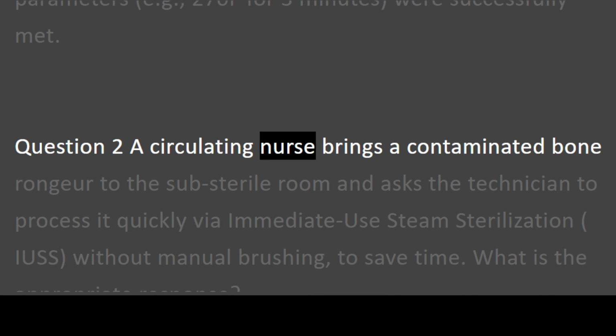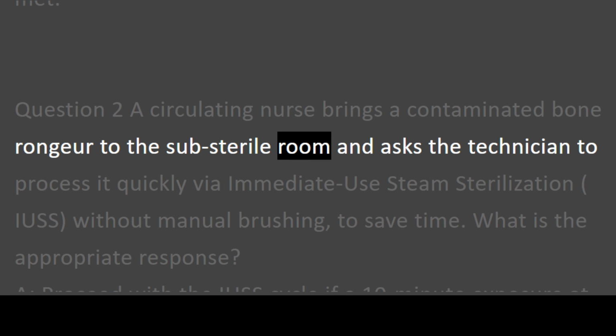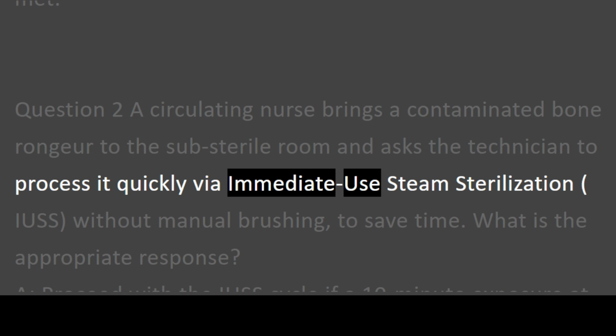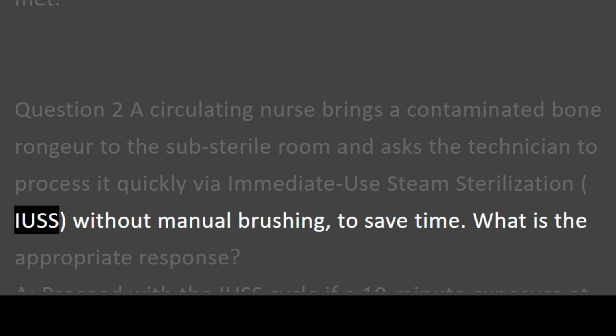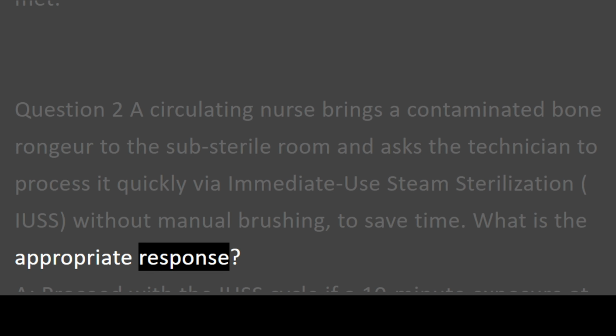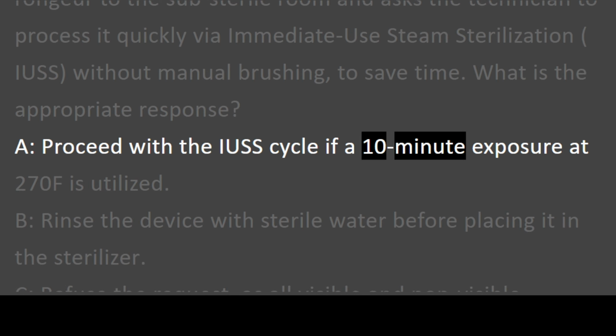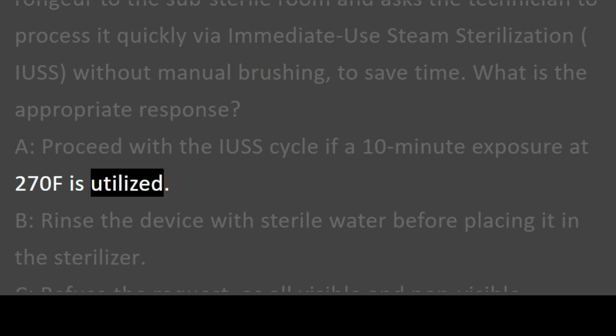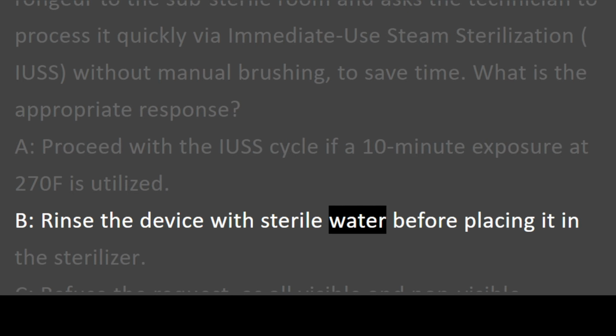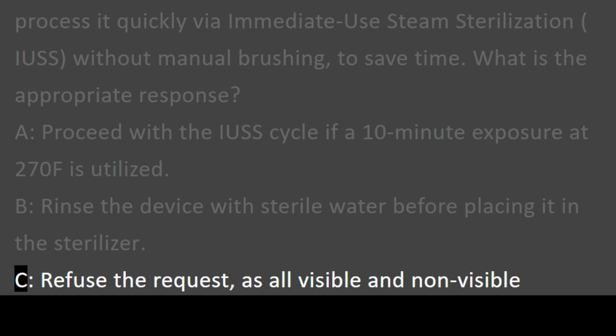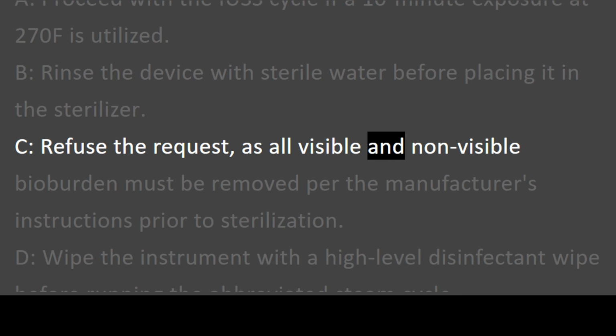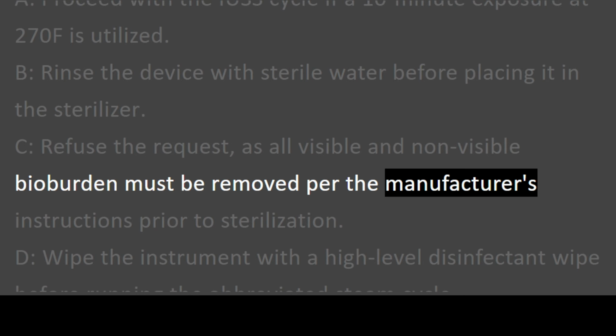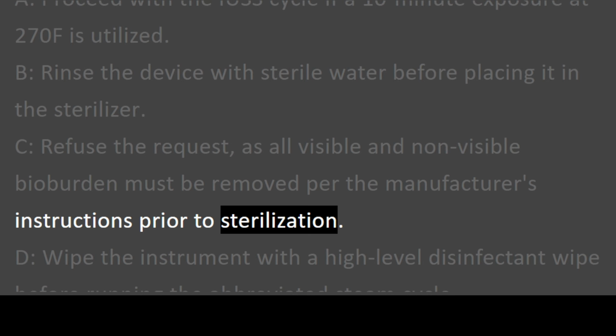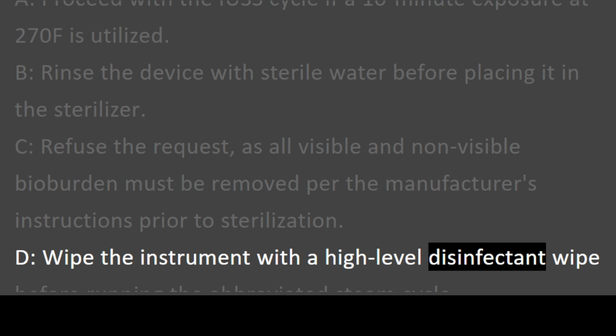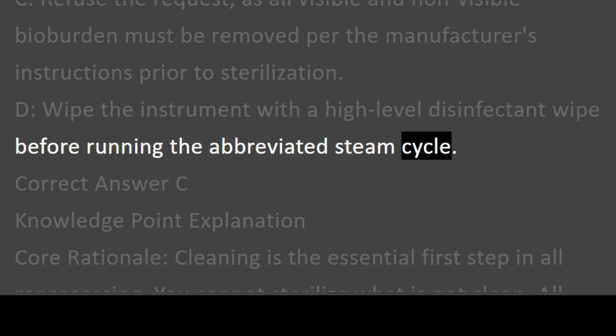Question 2. A circulating nurse brings a contaminated bone rongeur to the substerile room and asks the technician to process it quickly via immediate use steam sterilization, IUSS, without manual brushing, to save time. What is the appropriate response? A. Proceed with the IUSS cycle if a 10-minute exposure at 270F is utilized. B. Rinse the device with sterile water before placing it in the sterilizer. C. Refuse the request, as all visible and non-visible bioburden must be removed per the manufacturer's instructions prior to sterilization. D. Wipe the instrument with a high-level disinfectant wipe before running the abbreviated steam cycle.